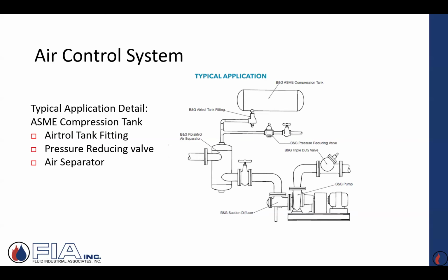You decided to lose the air cushion. Now all of a sudden, you just got a tank full of water. Boiler turns on, no place to go. Relief valve dumps. Facilities people come over. They've got to mop up the water. They're all frustrated or whatever. So this system, years ago, they never used air vents.